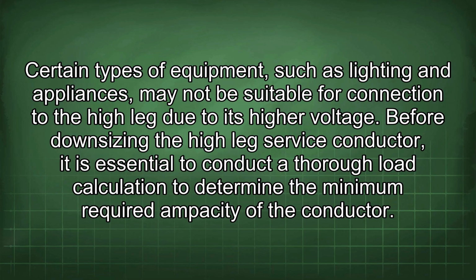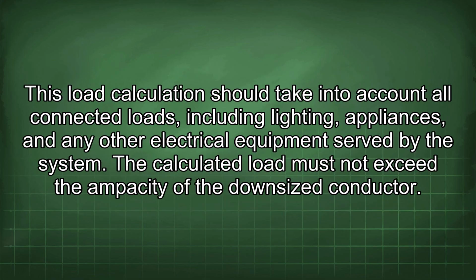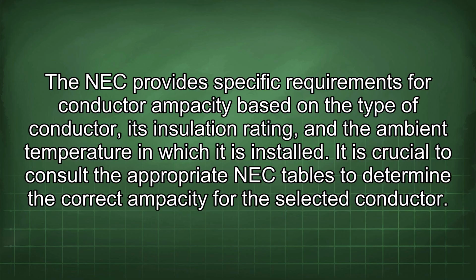to its higher voltage. Before downsizing the high leg service conductor, it is essential to conduct a thorough load calculation to determine the minimum required ampacity of the conductor. This load calculation should take into account all connected loads, including lighting, appliances, and any other electrical equipment served by the system. The calculated load must not exceed the ampacity of the downsized conductor. The NEC provides specific requirements for conductor ampacity based on the type of conductor, its insulation rating, and the ambient temperature in which it is installed. It is crucial to consult the appropriate NEC tables to determine the correct ampacity for the selected conductor.